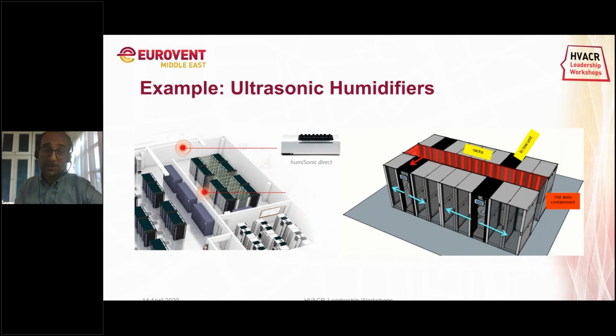Very often adiabatic technologies are room-based, for example, in this case, using an open area. Ultrasonic technology is basically using piezoelectric transducers and high frequency vibration to create small droplets of water, then collected by fans. Those fans are driving those small droplets of water, and these are almost instantly absorbed by the air, thus increasing its humidity without using a lot of energy. Why room-based? Because it's adiabatic. Room-based, or sometimes small air handlers, so in ducts or other areas, it's not very easy to put them into CRAC units due to airspeed and space. Space is essential for this type of units.